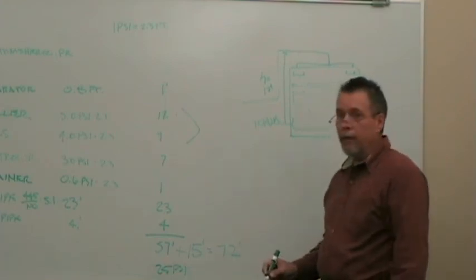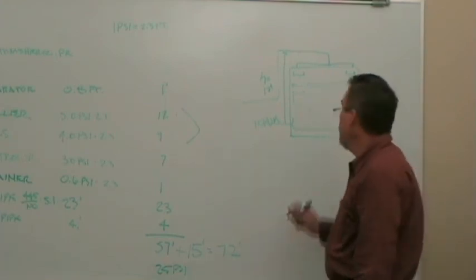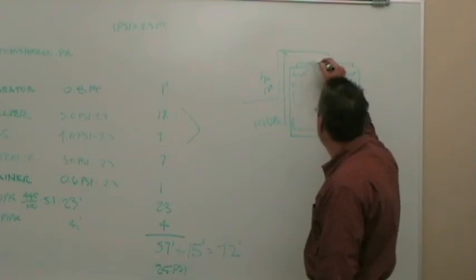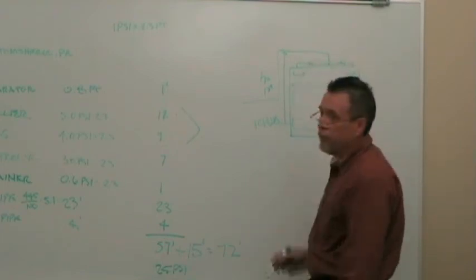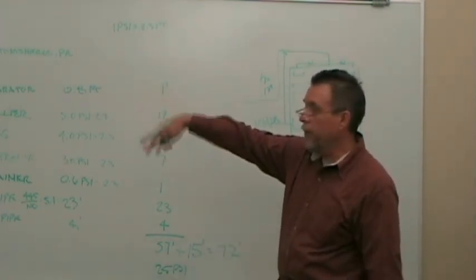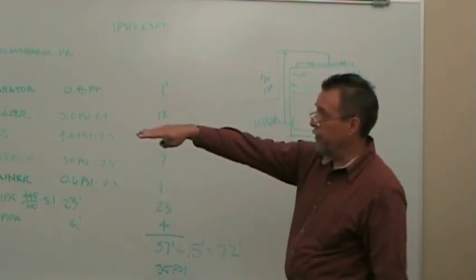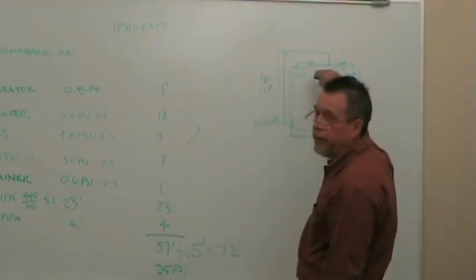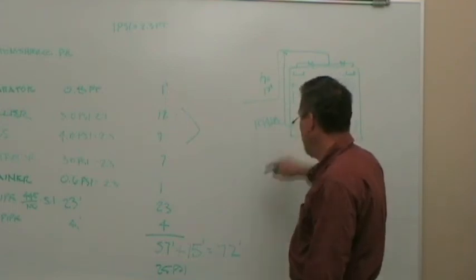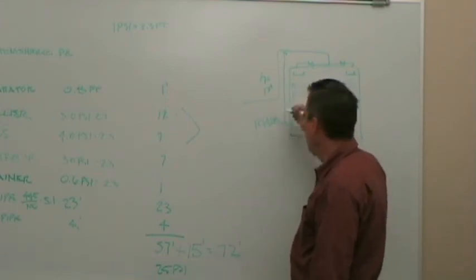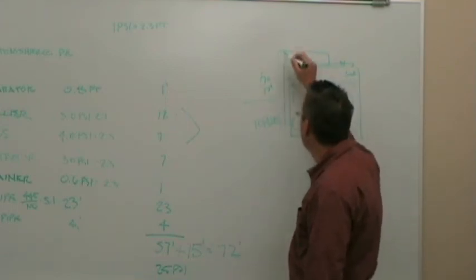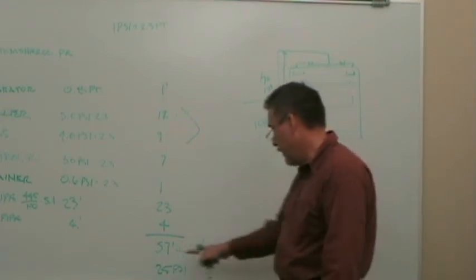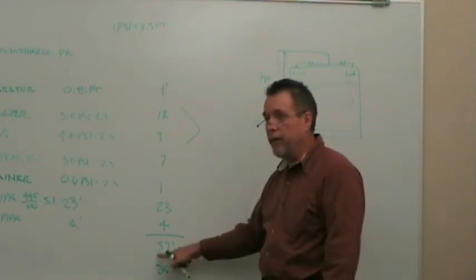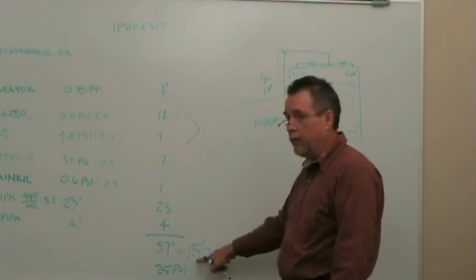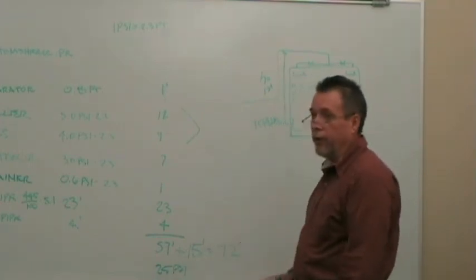Do you take any consideration of your balancing valves on top of your tower? Yeah, you might have some more balancing valves here. They would just figure into your piping loss. Same calculation we went through. Got the valves at the chiller, valves at the cooling tower. But then, since I've got an open cooling tower, I had to figure this H in right here, the lift. So whatever my pipe loss and fitting loss I have, add the actual lift for a cooling tower pump.